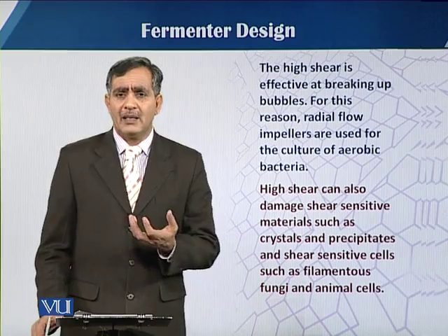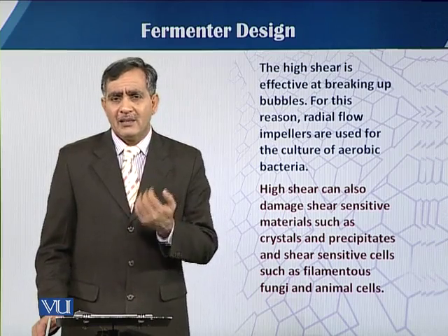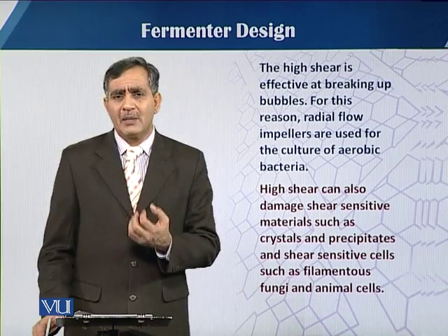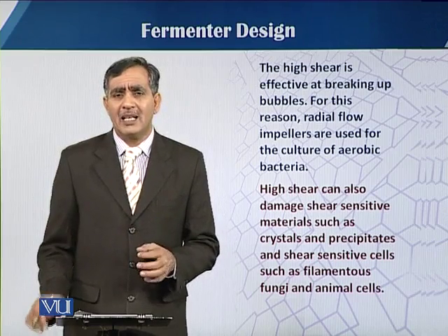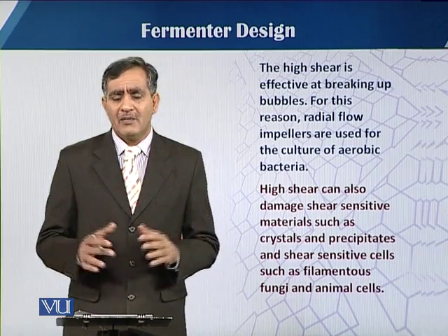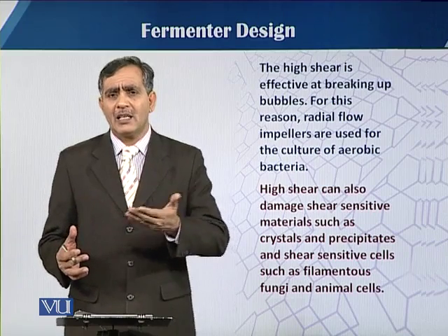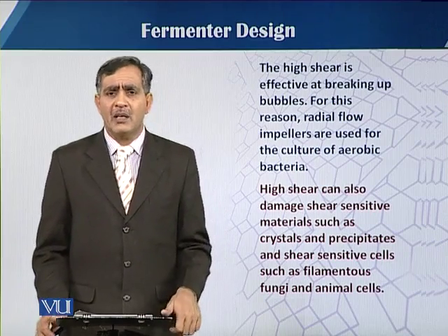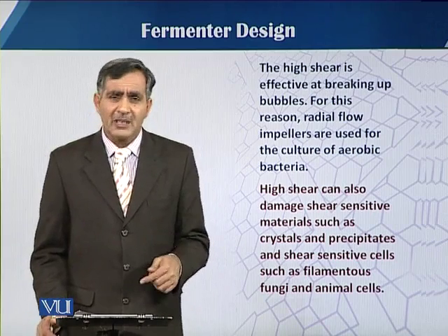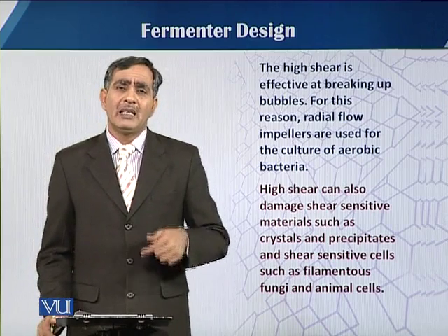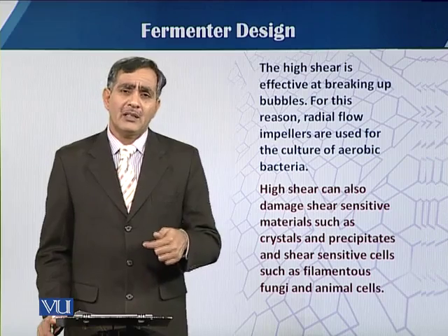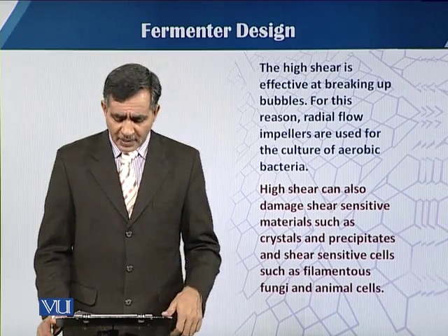When we supply the air, the more the bubble size reduces, the more surface area there is, and the more chance of oxygen solubility in the medium. This is very positive. That's why selecting radial flow impellers is a positive factor.